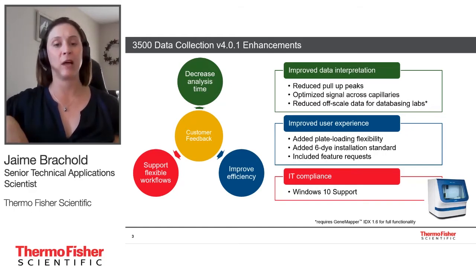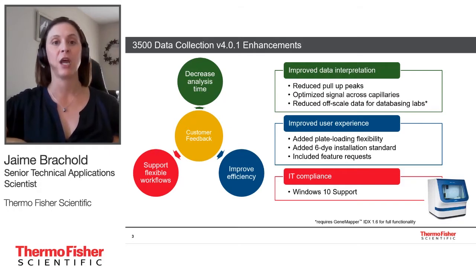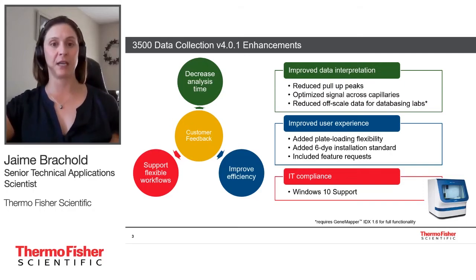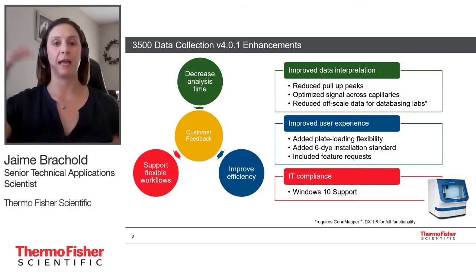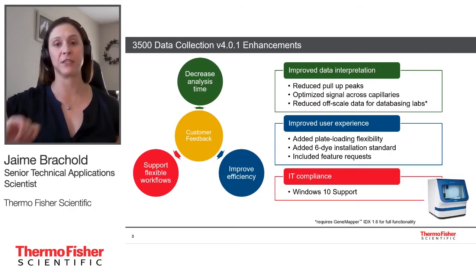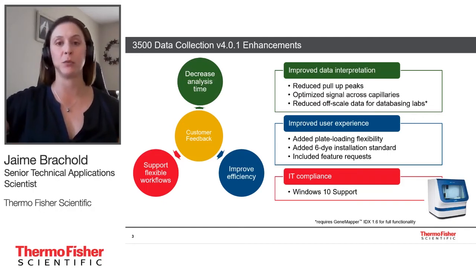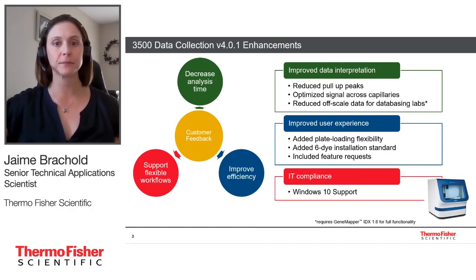Off-scale data recovery lifts the cap off the top end of the dynamic range. Currently your data is capped around 32,000, but if you're running with off-scale data recovery, that cap is lifted up to about 65,000. You will also see pull-up related to off-scale peaks reduced. GeneMapper IDX version 1.6 is required for full functionality — it's only in version 1.6 that you'll see that cap lifted to 65,000. In earlier versions of IDX, you will still see reduced pull-up, but you won't see that cap lifted.